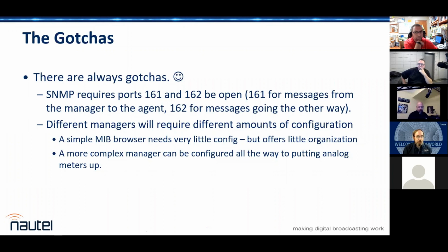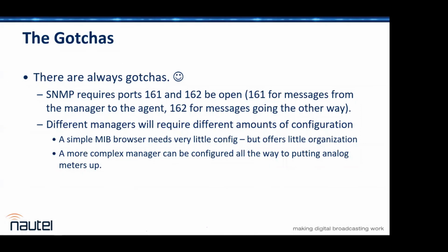But the big thing is getting the MIB files. And I say, we put ours on the website. Not everybody does, so you do have to chase them sometimes. That's the only big challenge, just getting the MIB files. Once you've got those, I like the iReasoning browser because I can load the MIB file into it and scroll through it and get all my OIDs, and then manually load them into whatever manager I happen to choose to use. So, multiple tools for the job. It just really depends on what you want to accomplish.